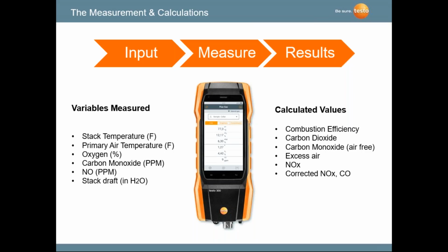From there, we calculate combustion efficiency. That's determined by how well the burner is operating, basically your air and your fuel input, and making sure that you have safe and efficient combustion. We're calculating carbon dioxide, which is a byproduct of combustion, and we're calculating other things that are necessary for boiler maintenance and furnace maintenance.